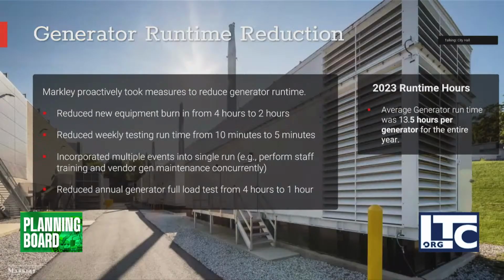Some of the proactive measures we've taken to accommodate concerns of the neighbors regarding running our equipment: we've reduced the burn-in time required when we install new equipment from 4 hours to 2 hours. We've reduced our weekly testing time from 10 minutes to 5 minutes. We've tried to combine events to avoid multiple uses of the equipment, and we've reduced our annual load test from 4 hours to 1 hour. So we've really made efforts to accommodate concerns we've heard from the neighborhood.